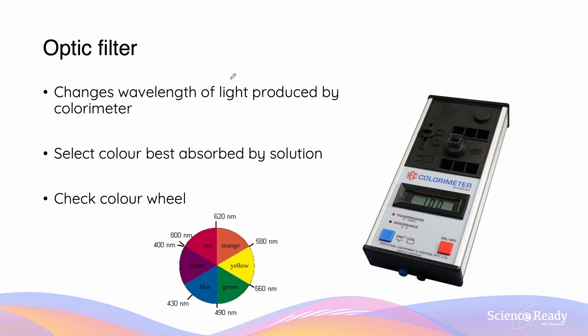The optic filter is what changes the wavelength of light produced by the colorimeter. We want to select the color that is best absorbed by the solution, so we need to check the color wheel. Again, using our example of the orange colored substance: looking at our color wheel, orange colored substances are going to absorb mostly blue light. So to analyze the sample, we are going to analyze how much blue light it absorbs, and thus we select the blue option.